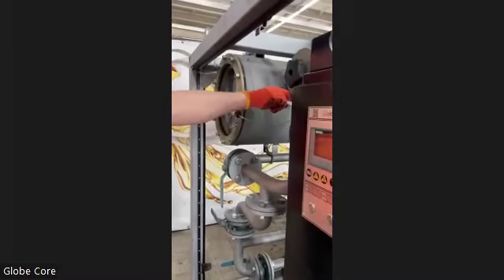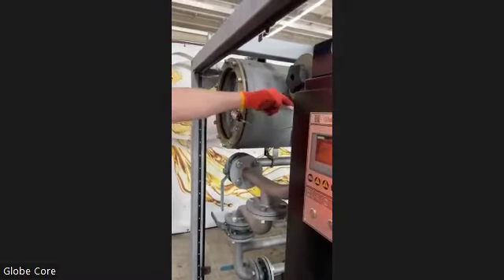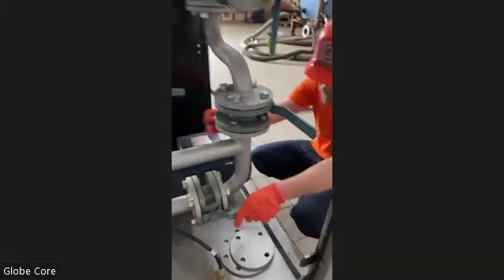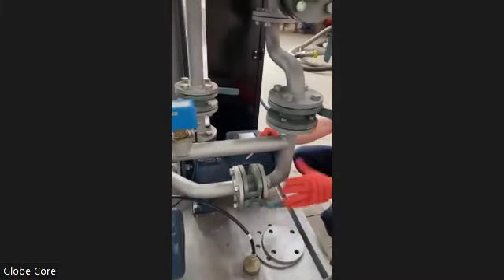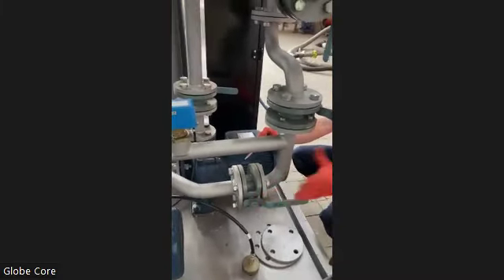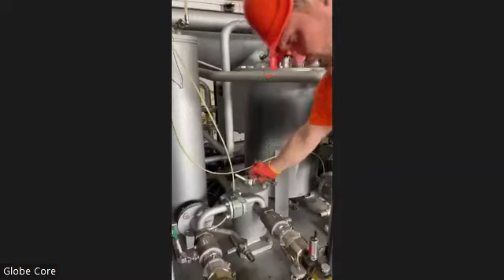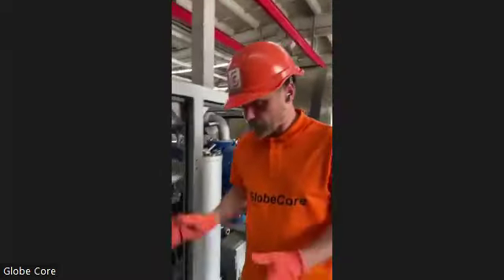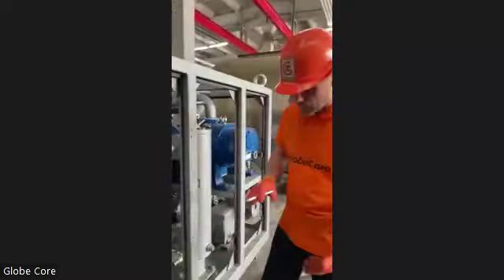We open the valve in here, and it allows us to bypass. This is the other end of this hose, and this allows us to bypass this cutting valve. Then we open the valve in here. So we vacuumize these pipes. Finally, we vacuumize the line with the heater, with the filter, and we get vacuum in here. So if we have vacuum in here, we can take oil from the tank with a low level of oil. So by means of this, you can fill the unit.